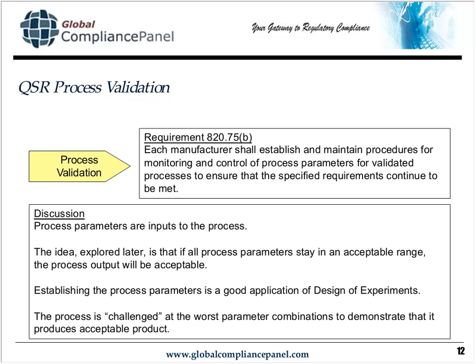The B part says you have to establish and maintain procedures to make sure these things continue to be met, and the preamble gives us a little bit about what's going on here. 820.75b, the preamble tells us, applies to performance of the process after validation. 75a is the initial validation of the process—that's what we talked about as the phases.